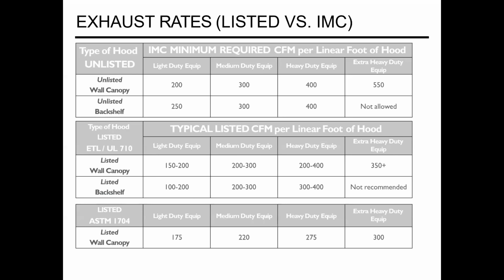And then ASTM 1704 is actually a performance standard. They did that testing based on what the Food Service Technology Lab did, testing all those hoods with and without end panels, and using a listed hood, pushing that equipment back. And this is kind of an average of what they had. So you can see even then, typically 150 is the minimum UL listing for light duty equipment. A lot of manufacturers will not do it at 150, but anywhere from 175 to 200 typically for a hood that's covering just a bunch of ovens.